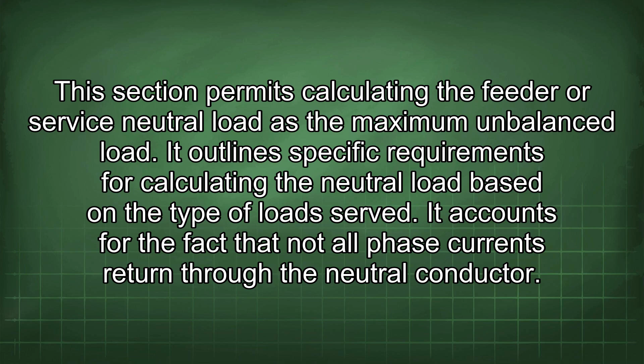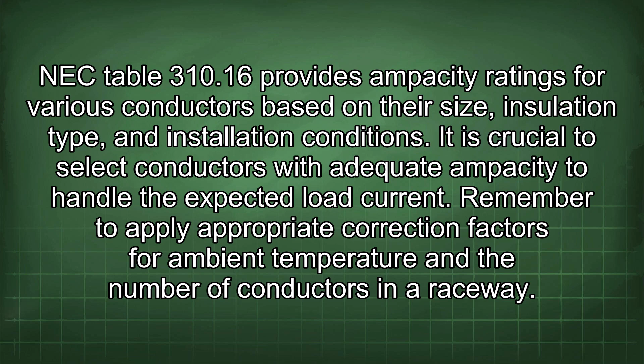NEC Table 310.16 provides ampacity ratings for various conductors based on their size, insulation type, and installation conditions. It is crucial to select conductors with adequate ampacity to handle the expected load current. Remember to apply appropriate correction factors for ambient temperature and the number of conductors in the raceway. NEC Article 250 covers grounding and bonding requirements.